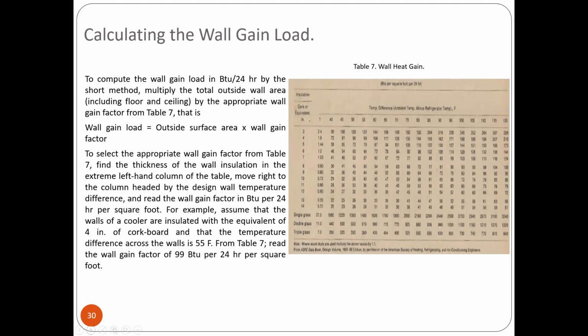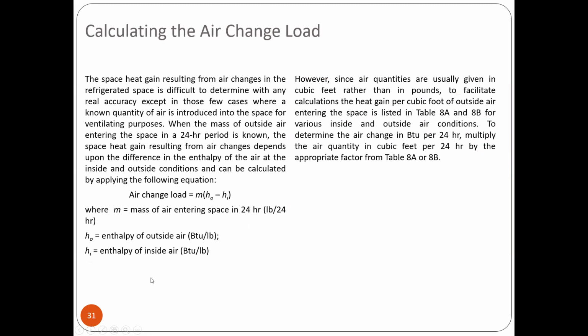So next, calculating now the air change load. Tapos tayo sa wall. So the space heat gain resulting from air changes in the refrigerated space is difficult to determine with any real accuracy, except in those few cases where a known quantity of air is introduced into the space for ventilating purposes. Yan, sa alam mo. When the mass of outside air entering the space in a 24-hour period is known, the space heat gain resulting from the air changes depends upon the difference in the enthalpy of the air at the inside and outside condition and can be calculated by applying the following equation.